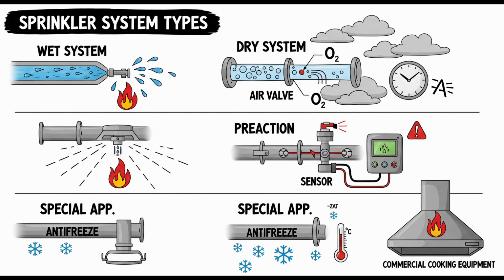Okay. Location and spacing of the detection devices are critical since they trigger the whole system. Absolutely. They must be installed according to their listing and the manufacturer's instructions, and they must cover all areas protected by the sprinkler system. And here's a key rule for systems triggered by thermal detection, like heat detectors or pilot sprinklers. The detection system's activation temperature must be lower than the activation temperature of the automatic sprinklers in that same area. Lower temperature for the detector than the sprinkler head.